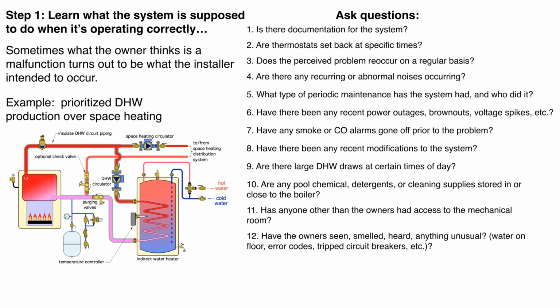Okay. Have any smoke alarms or carbon monoxide alarms been going off? Obviously, a carbon monoxide alarm going off is an urgent hint to take a look at that combustion system. Have there been any recent modifications to the system? Maybe you added a zone, maybe a burner nozzle was changed, maybe a control setting was changed. Are there large domestic hot water draws at certain times of the day? Again, pointing back towards this prioritized control.